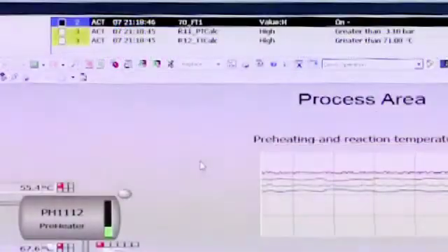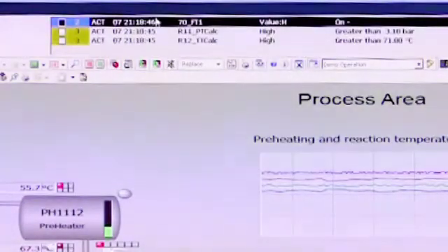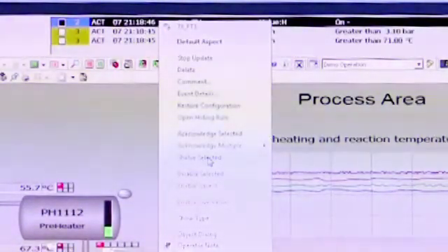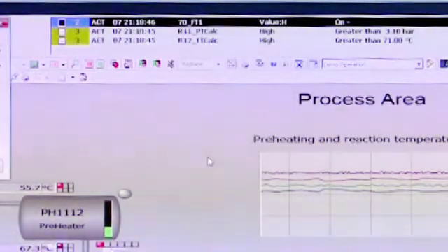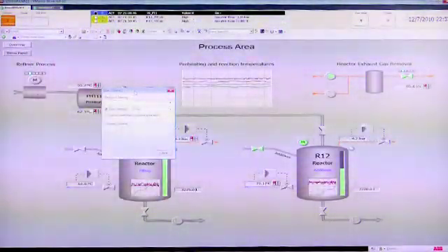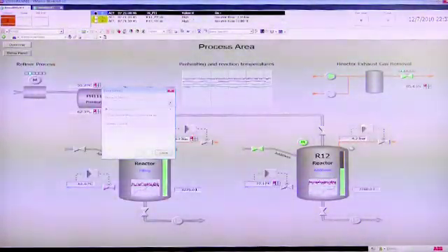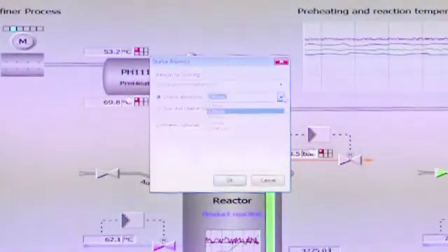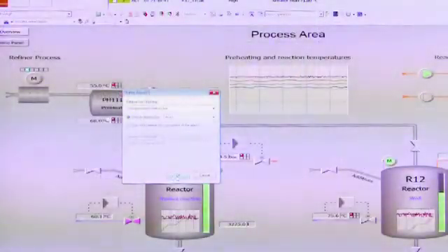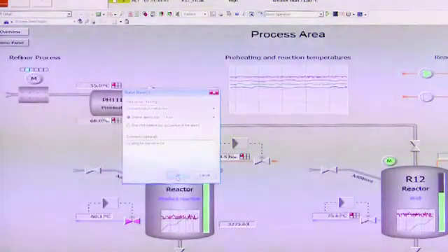The operator can shelve the alarm by right-clicking on the alarm and selecting Shelve Selected. This brings up a dialog where the operator can fill in the reason for shelving and the duration, and also put in comments. All of this gets captured in the audit trail.